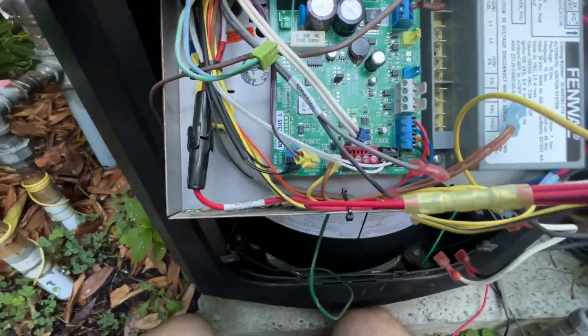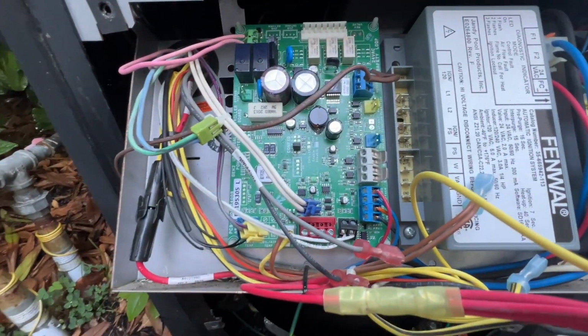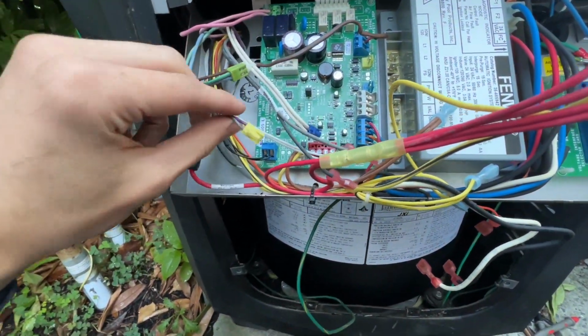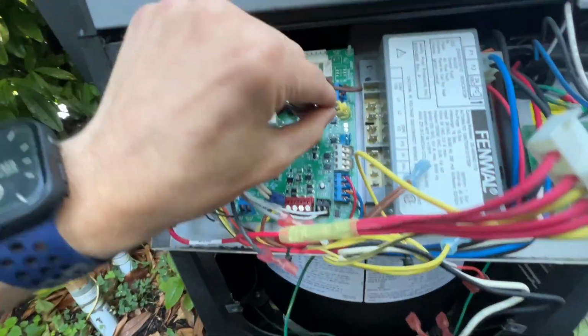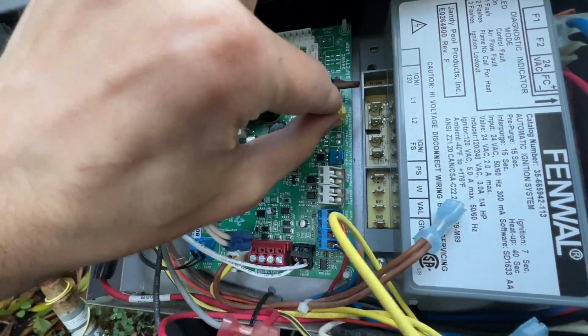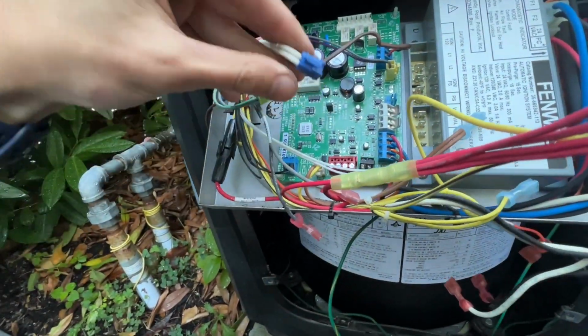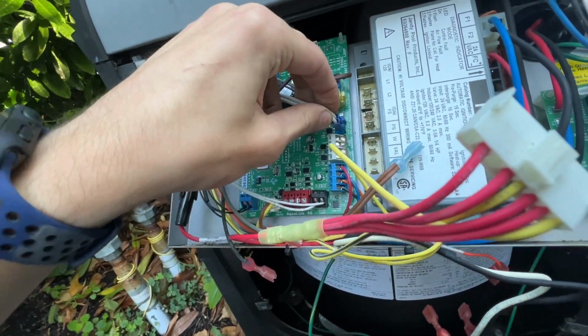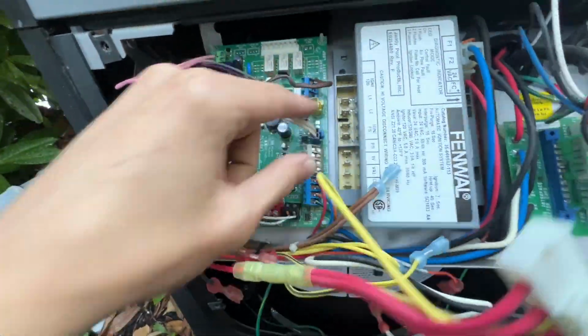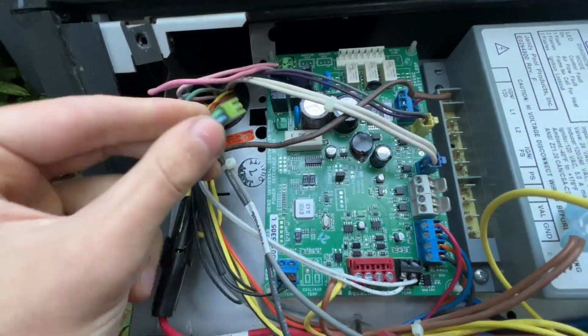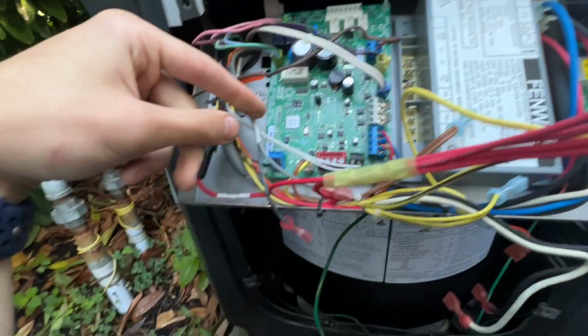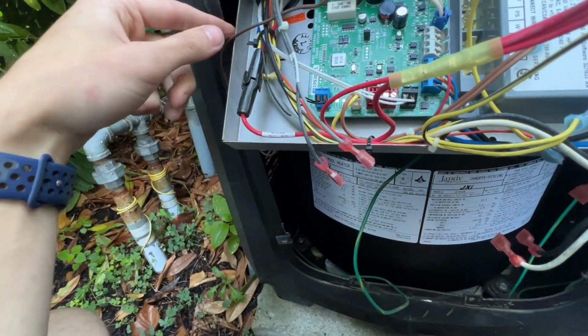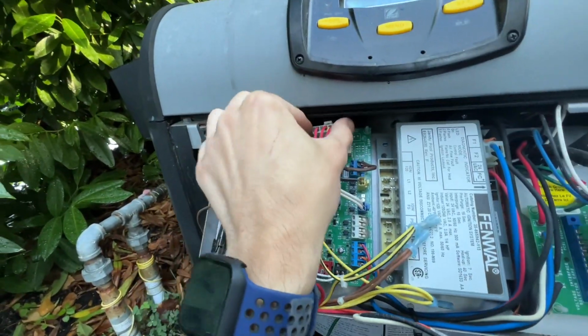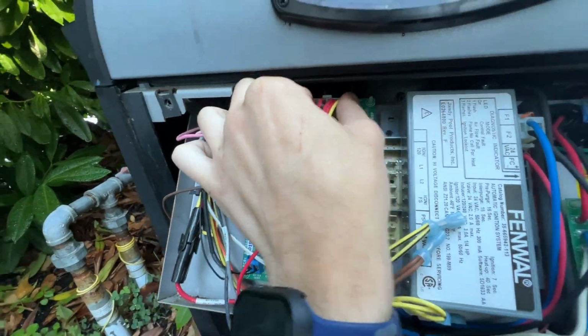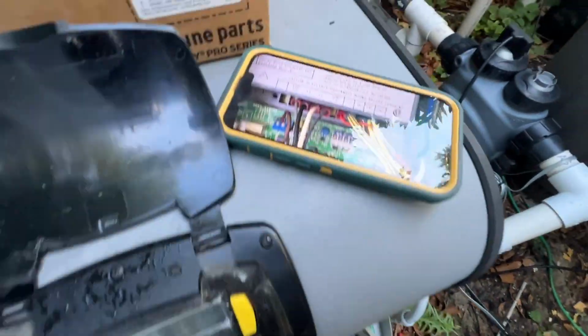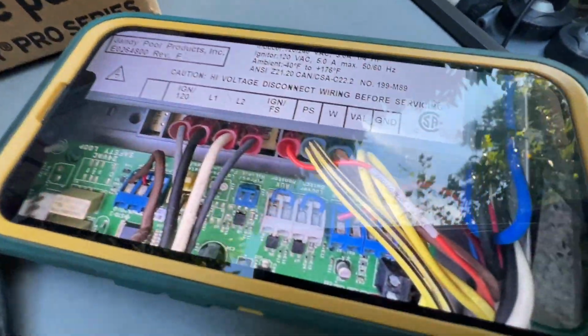Okay, so here is the new board. It's in place, and I've got all my loose wiring connected — the wires that didn't have direct plugs — and now I can start to plug in the wires that have plugs. So I have my water flow sensor, pressure sensor, flow sensor, our high pressure limit, and these are all color coded. We have our motor for our Versaflow bypass, our ignition, our pump, our 24 volt connection. So that's in there nice and tight. I took a picture of these just to make it easier to put it all back together.